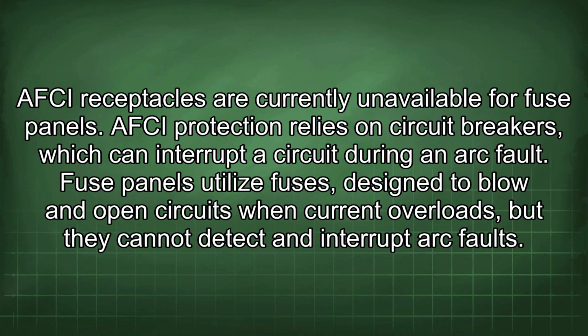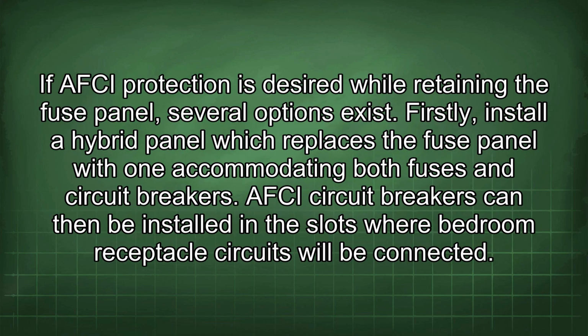AFCI receptacles are currently unavailable for fuse panels. AFCI protection relies on circuit breakers, which can interrupt a circuit during an arc fault. Fuse panels utilize fuses designed to blow and open circuits when current overloads, but they cannot detect and interrupt arc faults. If AFCI protection is desired while retaining the fuse panel, several options exist.